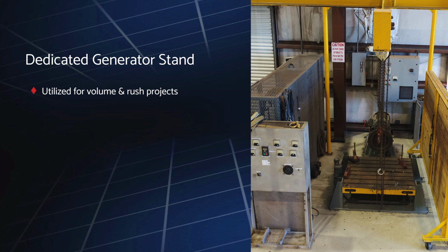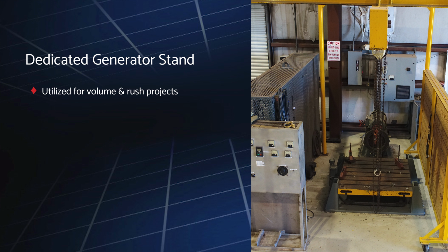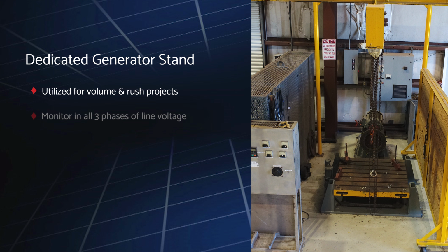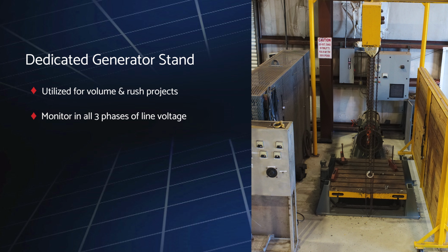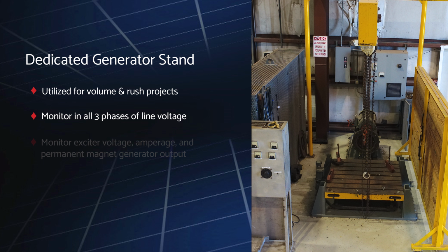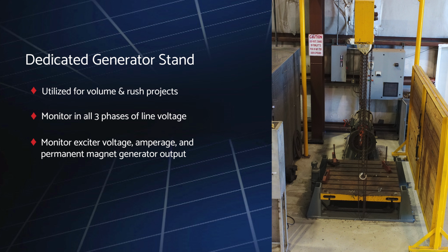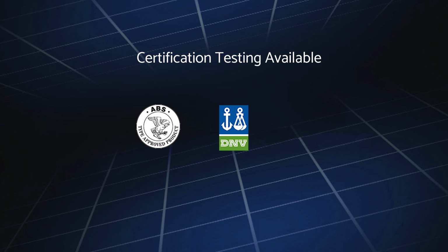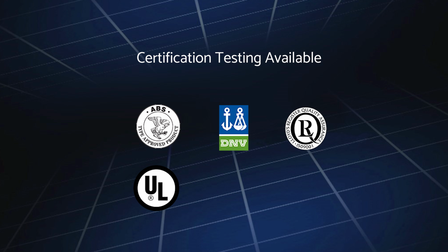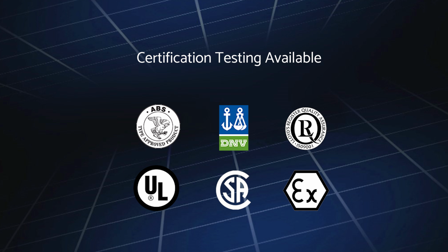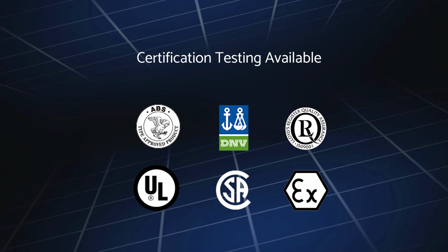We also have a dedicated generator test stand to accommodate volume and rush projects. The stand is capable of monitoring all 3 phases of line voltage, as well as exciter voltage, amperage, and permanent magnet generator output. Load testing on each stand is handled by our staff of highly trained technicians who work directly with customers to conduct critical industry certification testing.